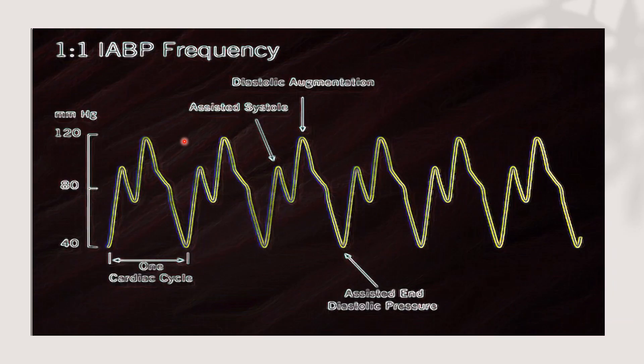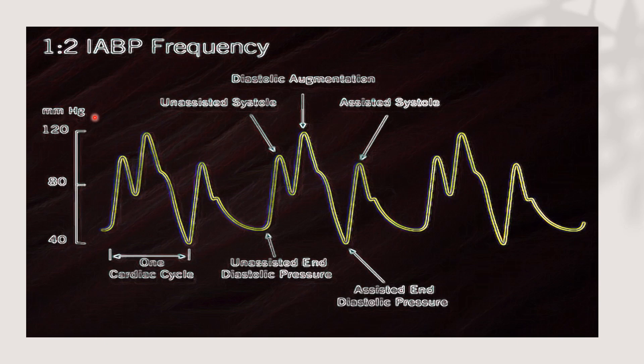One to one frequency means that each beat is assisted by the balloon. It is used when we start the balloon and the heart rate is less than 100. One to two means the first beat is assisted by the balloon and the second beat is not assisted — alternating: one assisted, one not assisted.